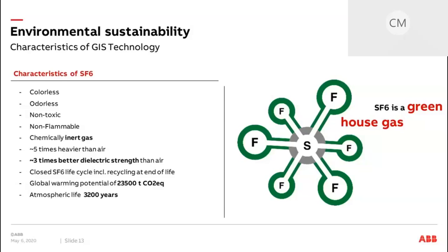It's 5 times heavier than air, but it also has a 3 times better dielectric strength than air, and that's the reason why GIS is so compact. Unfortunately, SF6 is a relevant greenhouse gas. So in case it gets released into the atmosphere, it has a global warming potential of 23,000 tons CO2 equivalent and an atmospheric lifetime of 3,200 years.